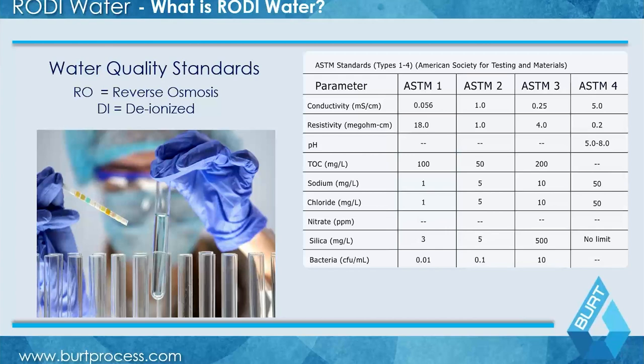You can see here the ASTM standards — ASTM 1, 2, 3, and 4 — with subgrades A, B, and C, as well as electronics grades. These come from a number of different parameters including resistivity, pH, TOC (total organic carbon), sodium chloride, mineral content, bacteria, and endotoxins. An RODI system is basically an engineered process system that incorporates a number of different technologies together to move you from your source water quality — city water or well water — to an end product water quality. Both of those parameters are really important early on in a project.